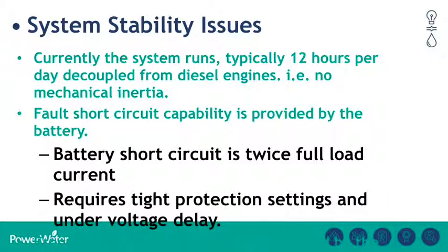The battery is only twice the full load capacity of the system, but we've been able to make that protection system work. It's adaptive - as soon as we switch back to a diesel grid, the protection settings change again, back up to settings appropriate for diesel.